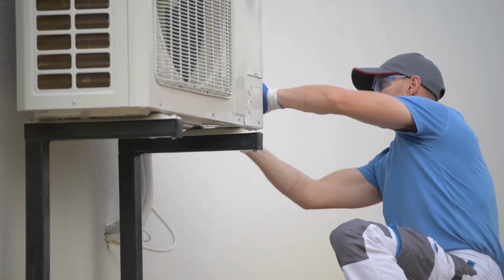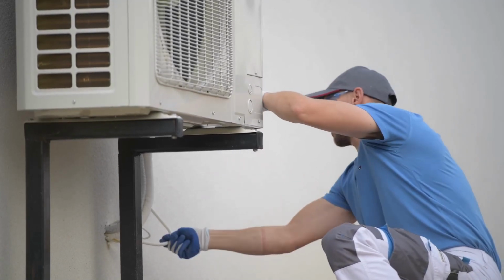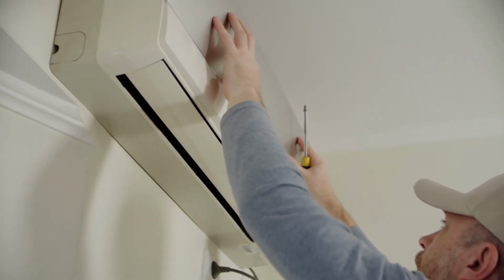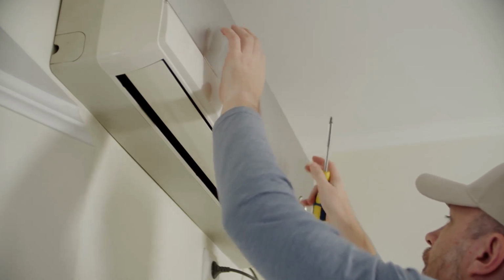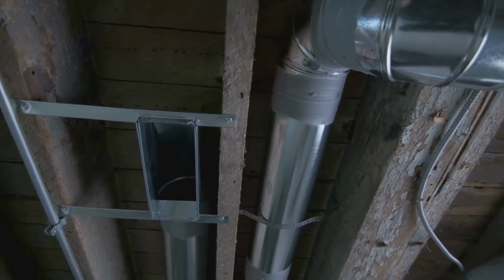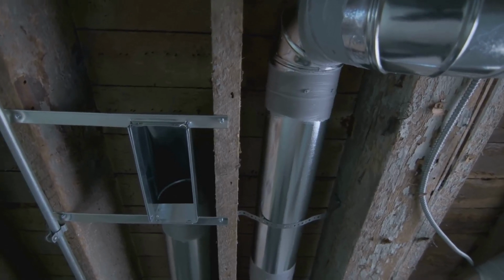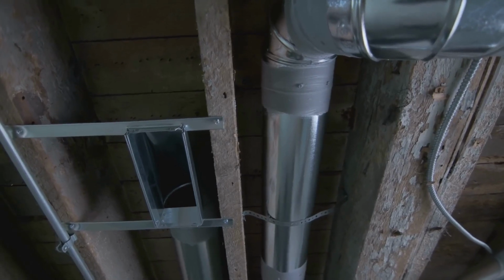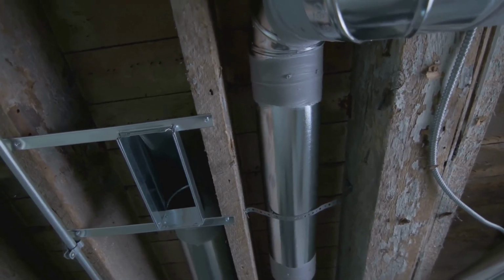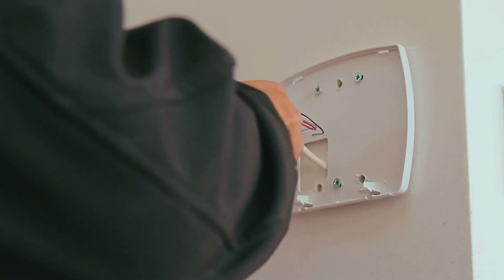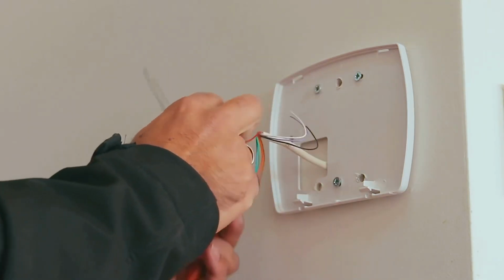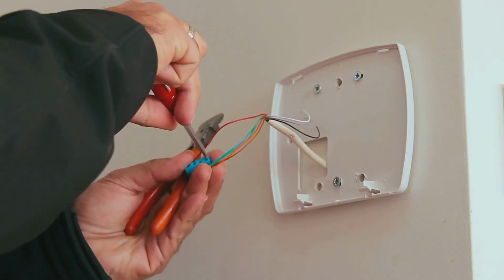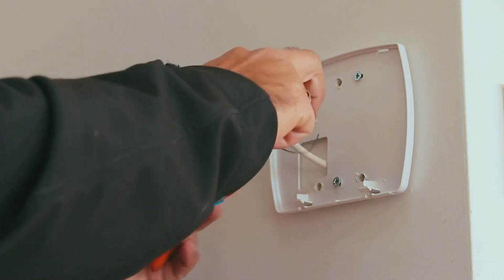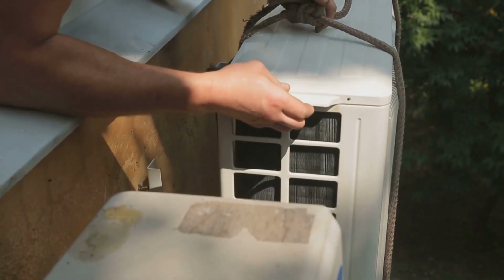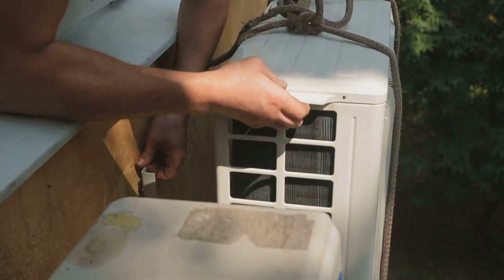Section 6. Indoor Unit Installation, Step-by-Step Guide. Alright, with your space prepped and ready, it's time to tackle the installation of the indoor unit. This usually involves mounting the unit on a wall or ceiling, connecting it to the electrical supply, and routing the refrigerant lines. First, mount the mounting plate. Begin by attaching the mounting plate to the wall or ceiling, using the provided screws or bolts. Make sure the plate is level and securely fastened to a stud or other structural support.